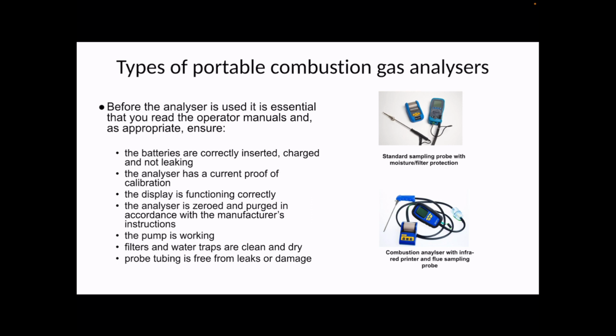And remember to purge the analyzer, usually in fresh air, but according to the manufacturer's instructions. Make sure the pump's working. You'll be able to hear that during the purge. You can hear the pump working. Make sure the filters and the traps are clean and dry, and that the tubing to the probes hasn't got any leaks or cracks in it, or any damage that would mean your readings would be affected.